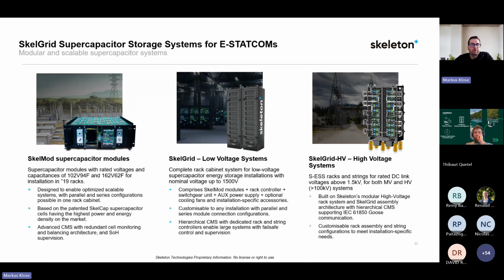So how does this look? You can see, for example, some modules - we call them SkelMod, supercapacitor modules. These go from voltages per module of 102 up to 162 volts, standard size made for 19-inch racks. And yes, you can put these onto ships and planes too, because supercapacitors can be discharged to 0 volts. It's actually a nice side effect of this technology that, in contrast to batteries, these systems do not have any residual energy left.